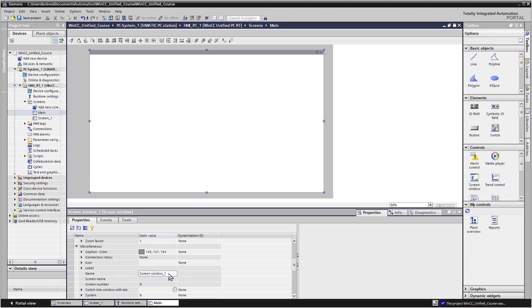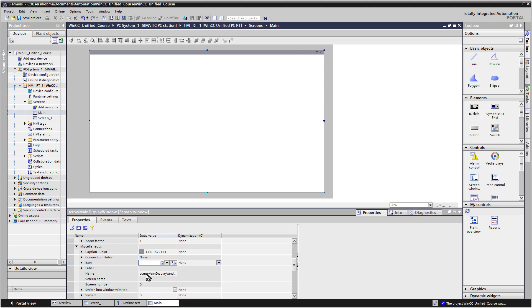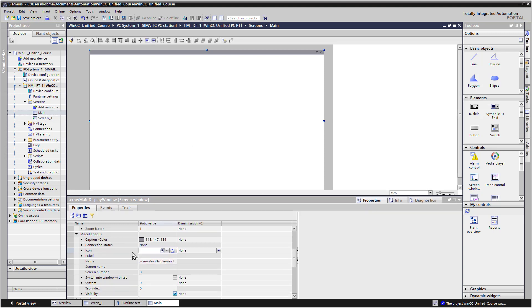So I like to use Hungarian notation. And basically, when you name an object such as a tag or a visualization object or a variable in scripting, if you use Hungarian notation, you can look at it and you know exactly what data type it is and a good idea of what it's used for. So the way we do this is the first few characters are all lowercase. And they indicate the type of the object or the data type. So this is a screen window. I'll just do SCRNW for screen window. And then we'll do one uppercase character. And I'll do Main Display Window. So if we look at this name, the first part of it tells us it's a screen window. And then Main Display Window kind of tells us what the function is.